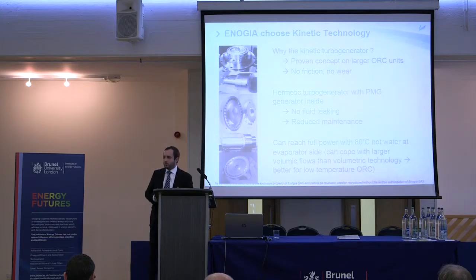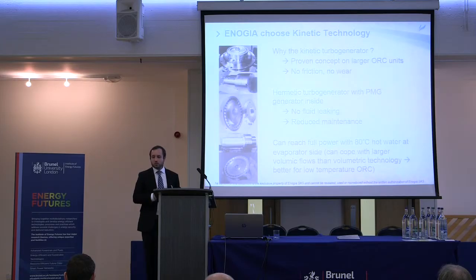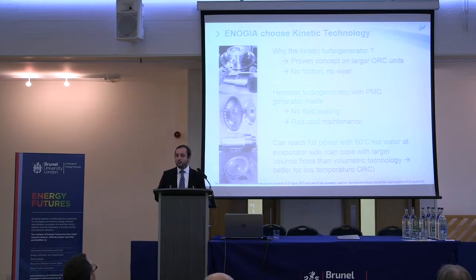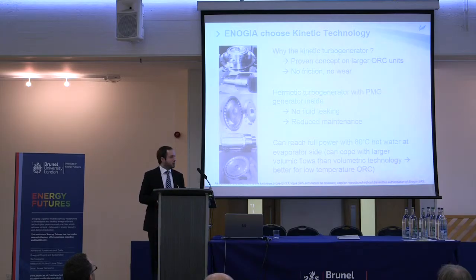Another very important thing regarding the kinetic turbine choice and low temperature ORC applications is the fact that volumetric expanders have limited volumetric capacity. So when running at lower temperature, you have higher volumetric flows. The good thing about the turbine unit is that we developed it so it can reach full power.